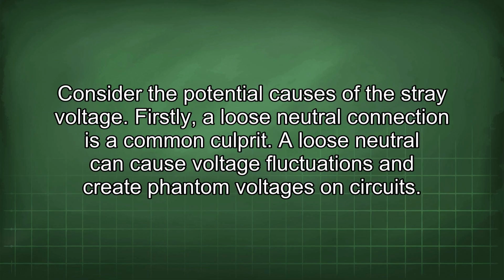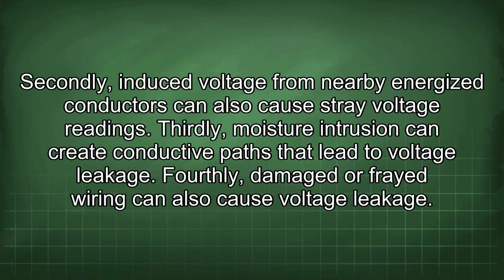Consider the potential causes of the stray voltage. Firstly, a loose neutral connection is a common culprit. A loose neutral can cause voltage fluctuations and create phantom voltages on circuits. Secondly, induced voltage from nearby energized conductors can also cause stray voltage readings. Thirdly, moisture intrusion can create conductive paths that lead to voltage leakage. Fourthly, damaged or frayed wiring can also cause voltage leakage.